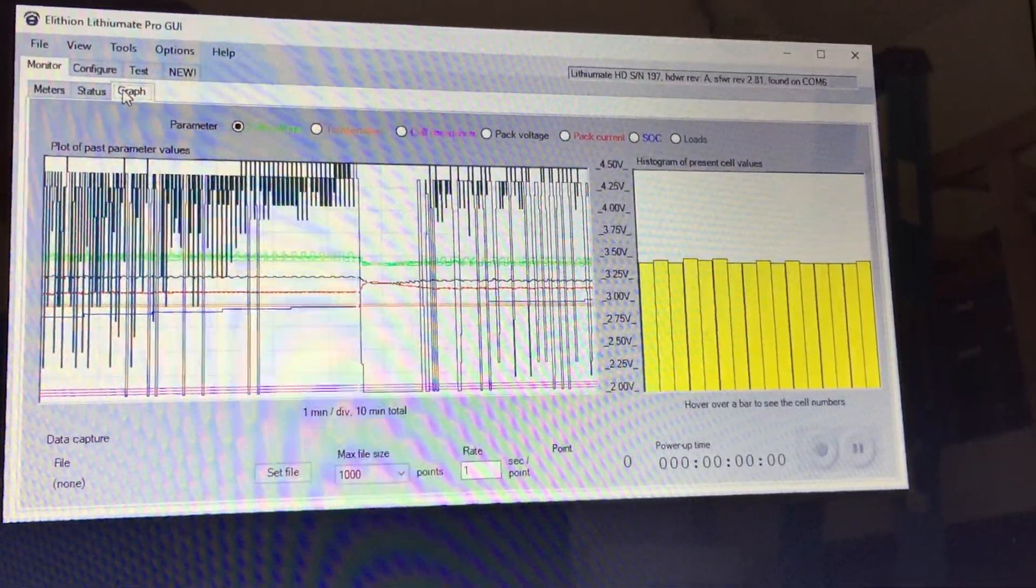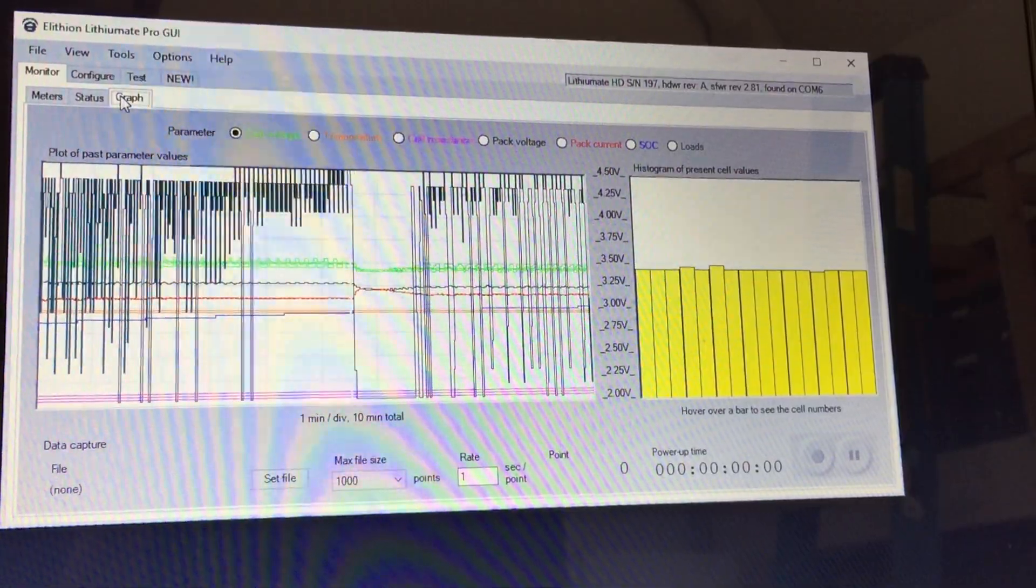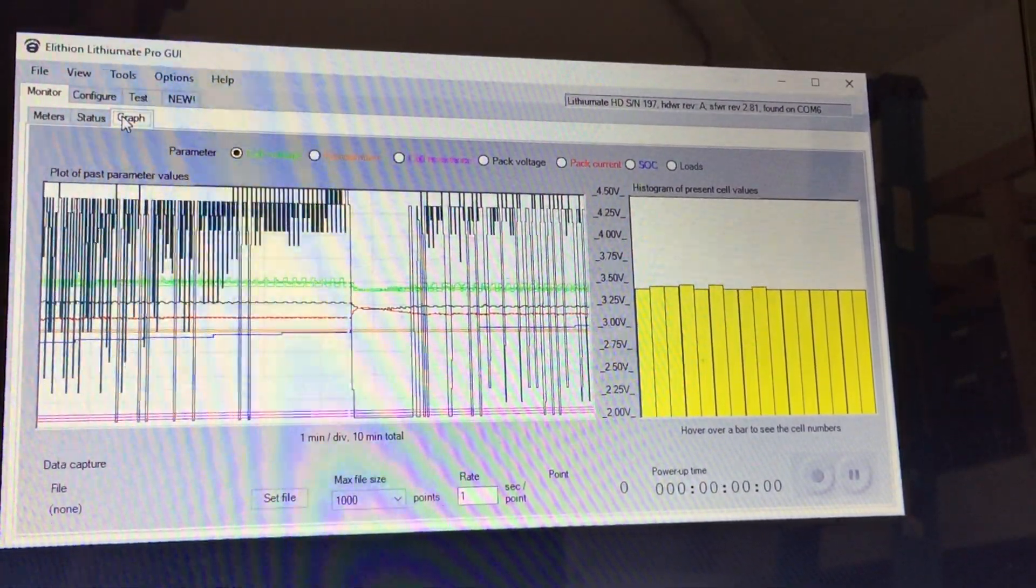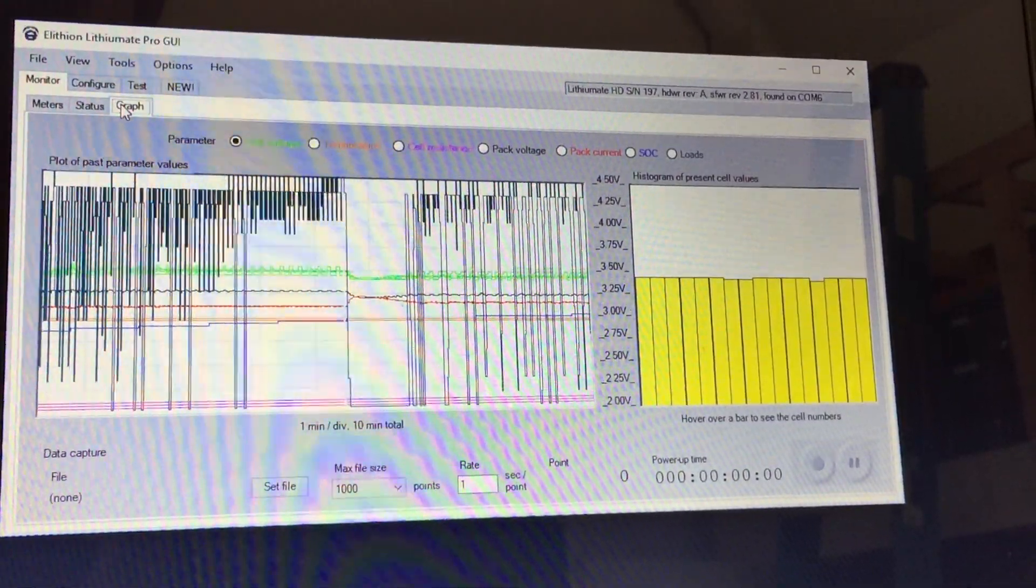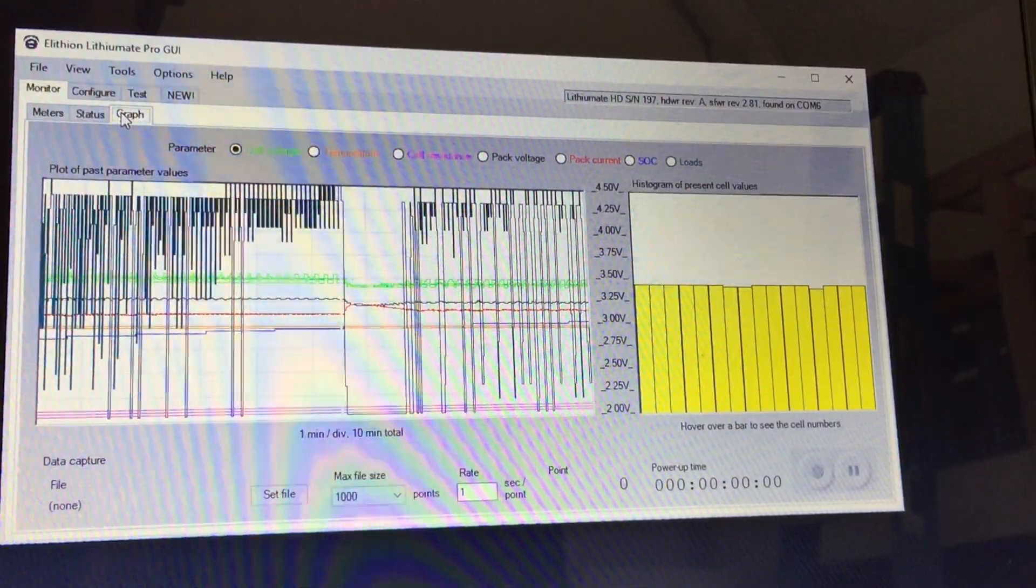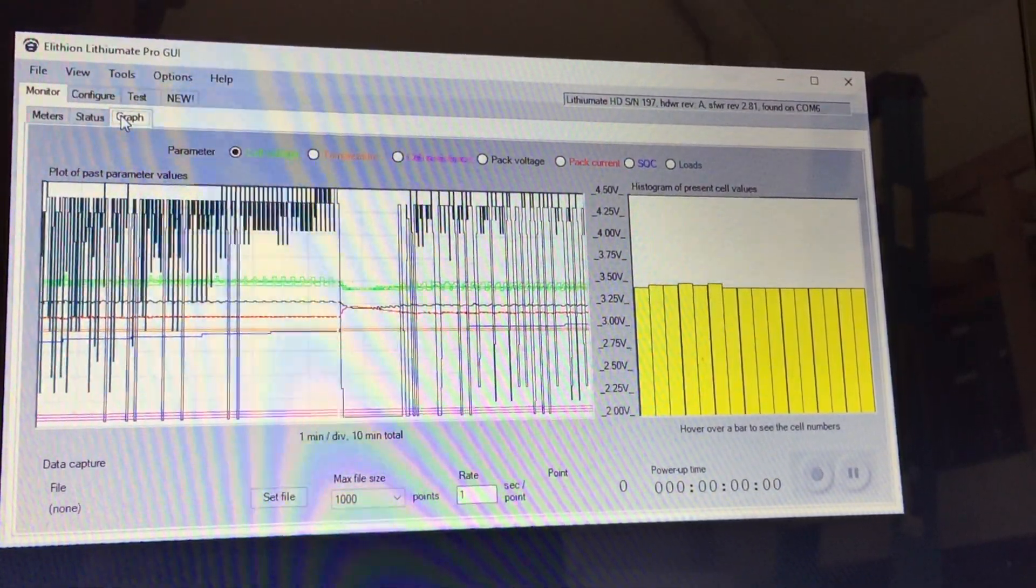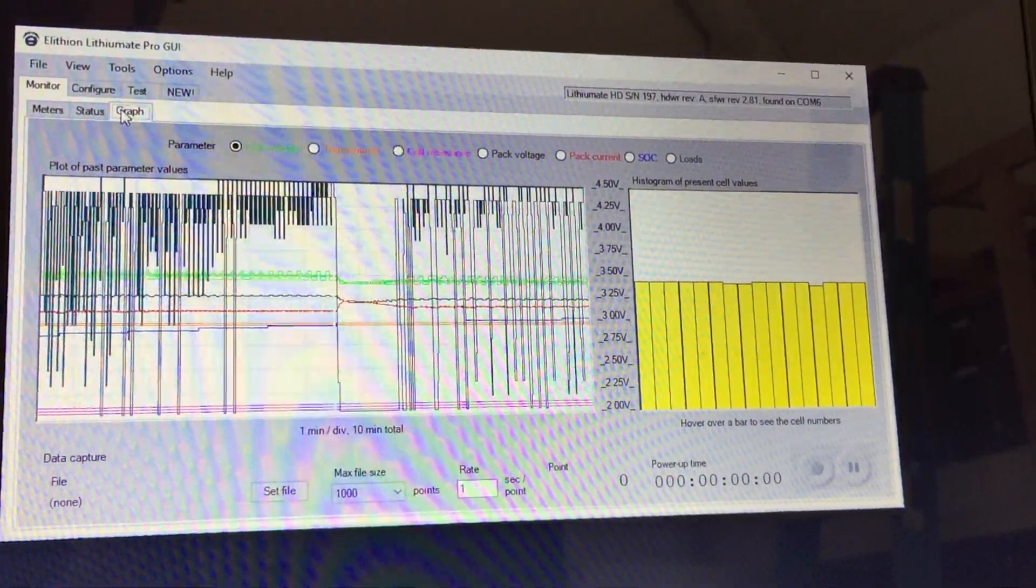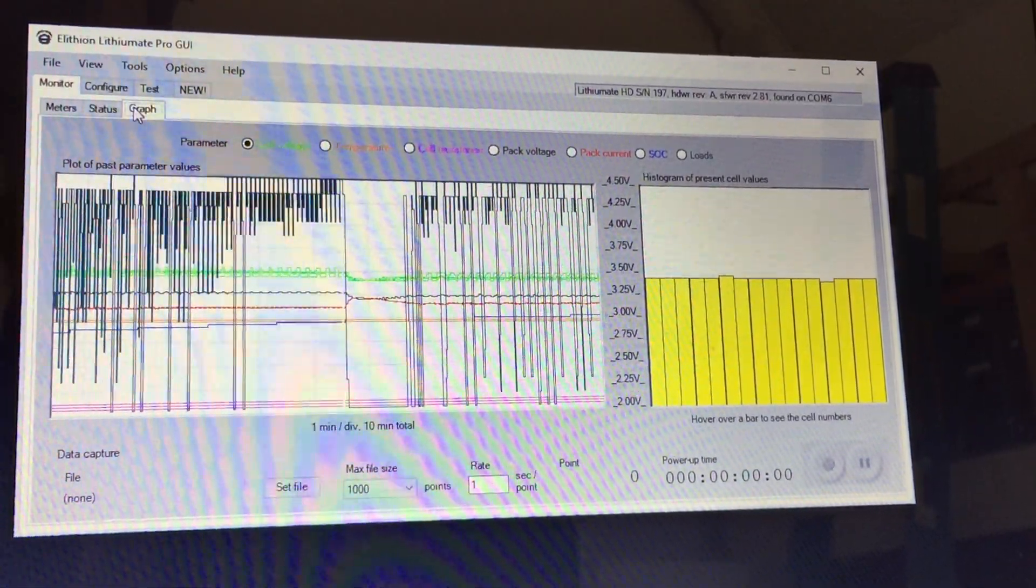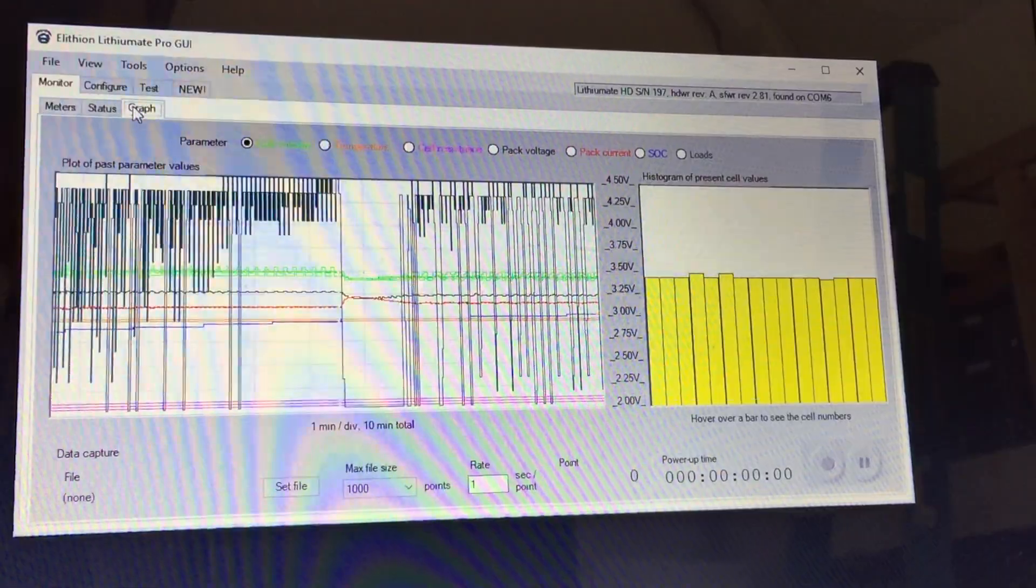It's pretty exciting stuff. Right now the battery management system is sending CAN bus messages to the Sunny Island inverter, including state of charge, maximum charge rate, and would send any warning or fault signals to the Sunny Island rather than opening up the onboard protective contactor. So this is a lithium iron phosphate battery to SMA Sunny Island full integration.